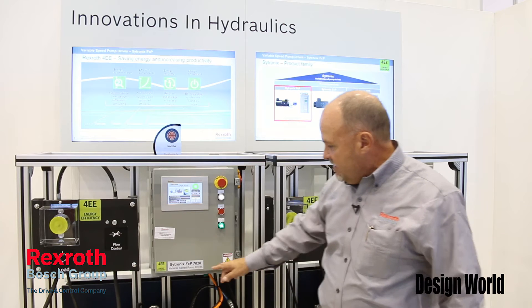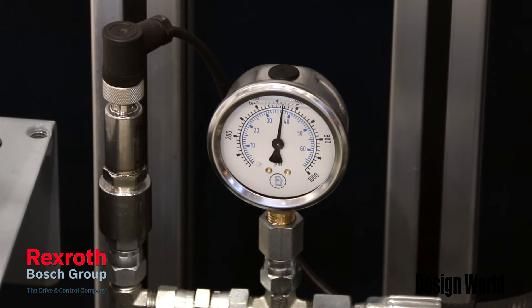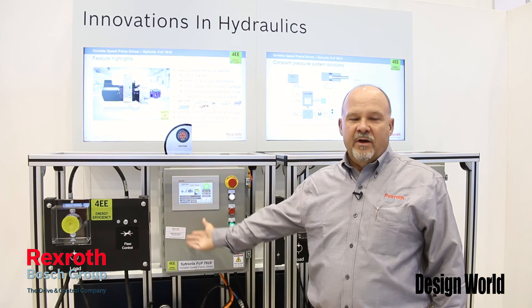You can see down below that the gauge in the energy-saving mode is running a little bit over 200 psi, but when we go to normal operating mode, it's running at a standard relief value of approximately 600 psi. That difference in pressure means that there's energy savings going on.